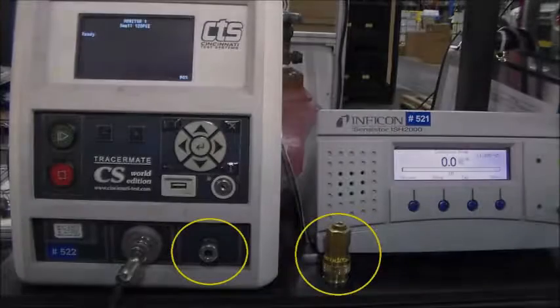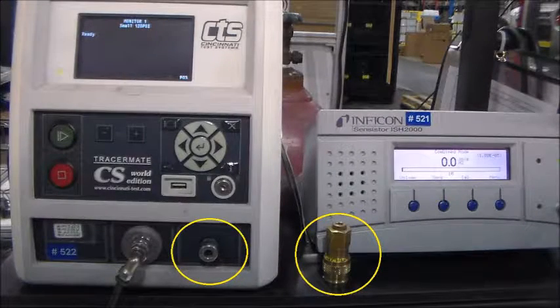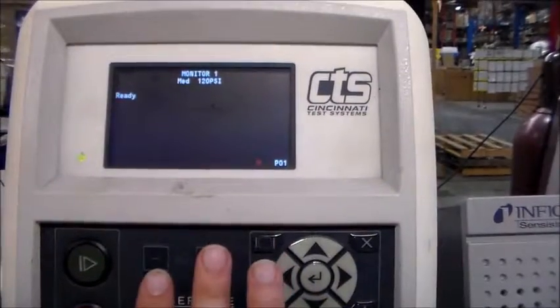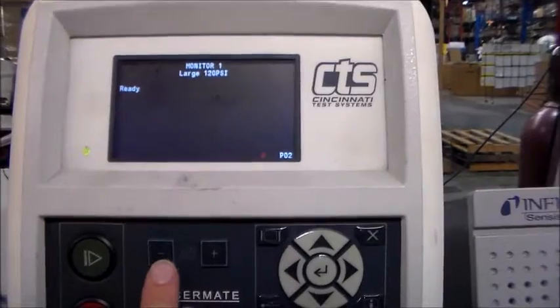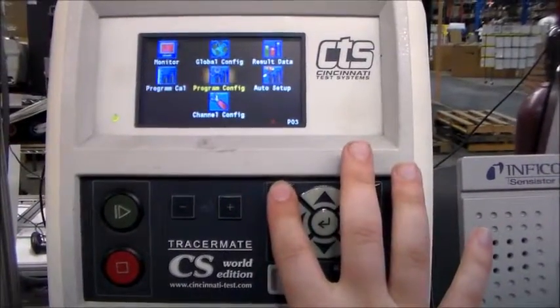The TracerMate must also be self-tested at the beginning of every week and must be auto-calibrated to the unit you are making every day or before starting a new run. To self-test the TracerMate, make sure the machine is on and replace the testing hose with the self-test plug on the front of the machine. Select the program indicated on the method sheet using the plus or minus buttons. Adjust the gas pressure by pressing the menu button.